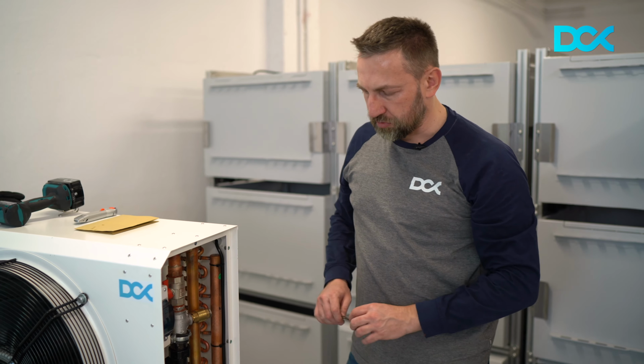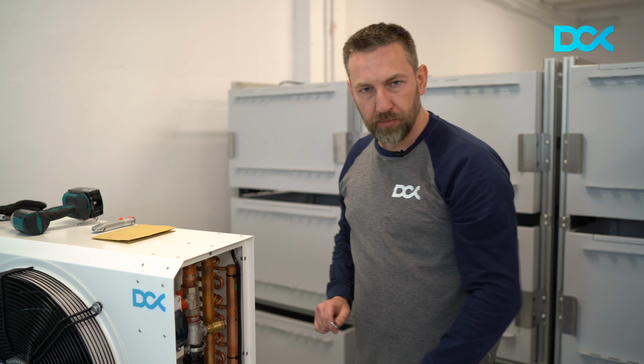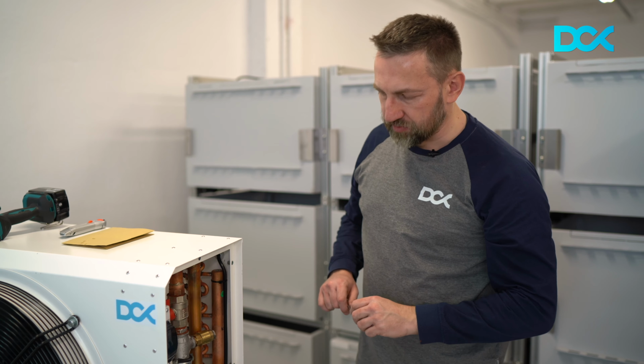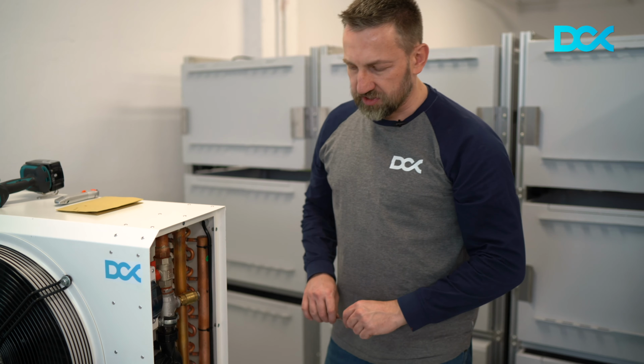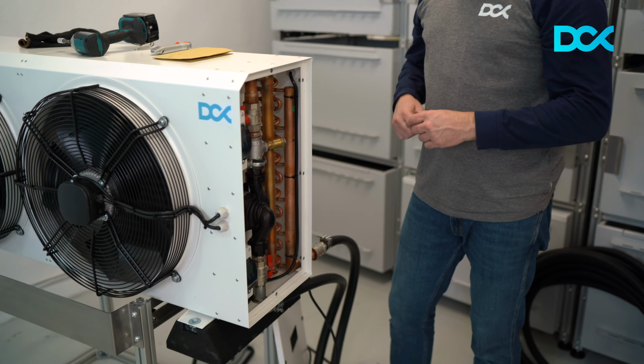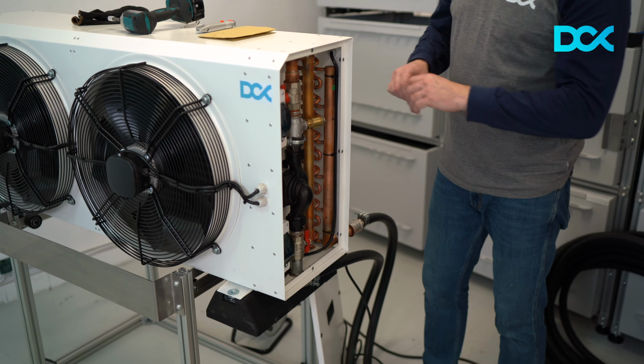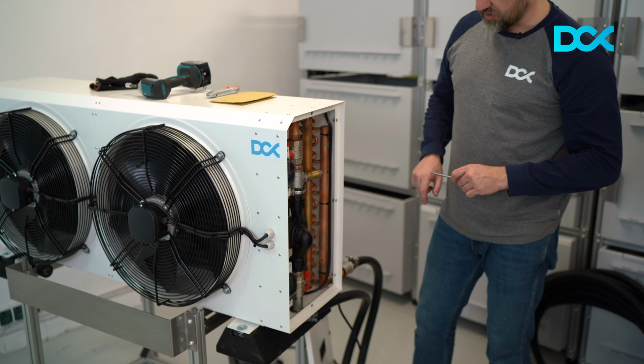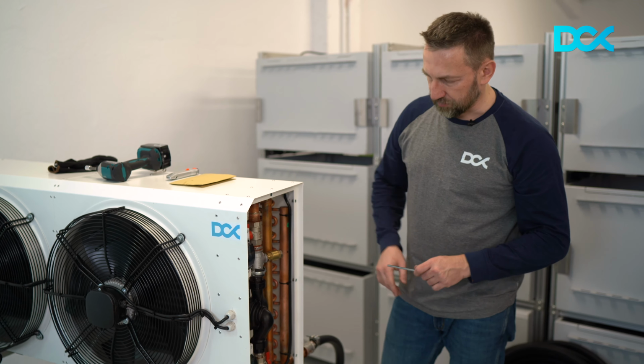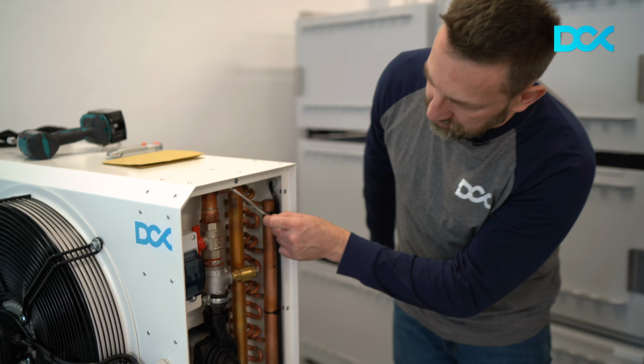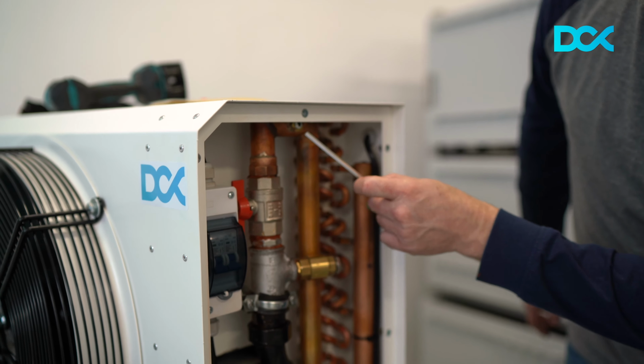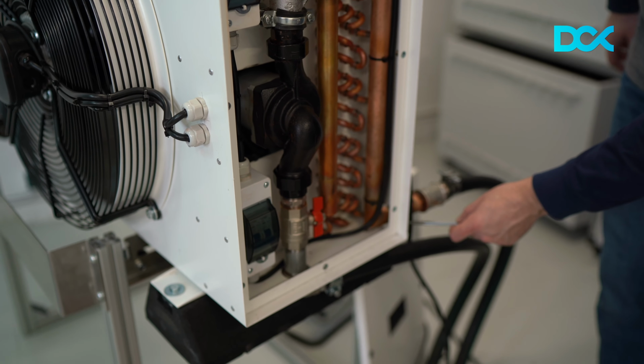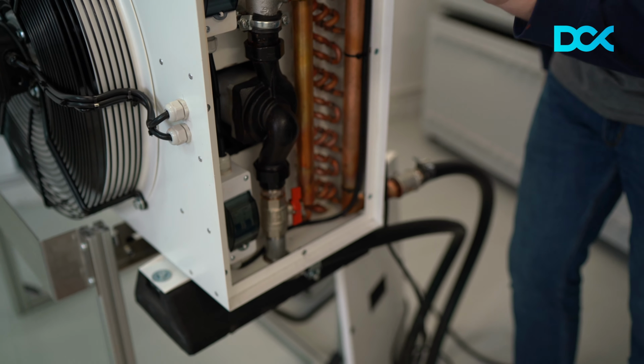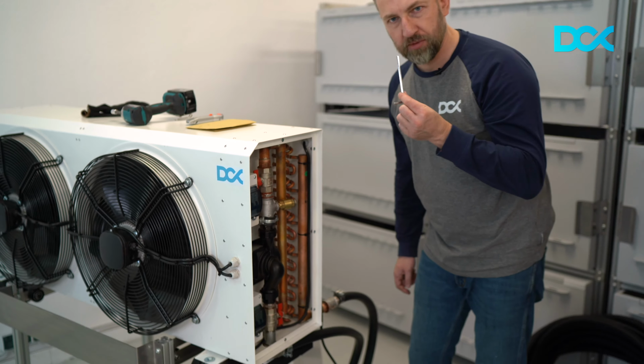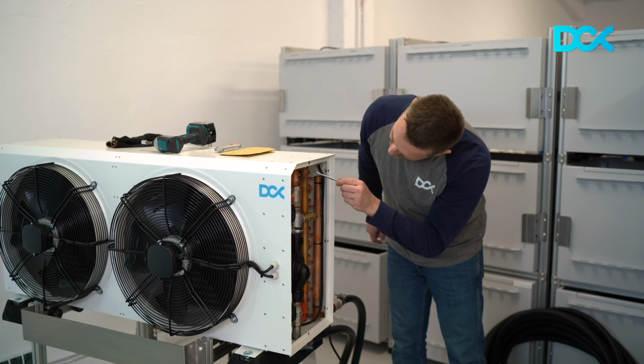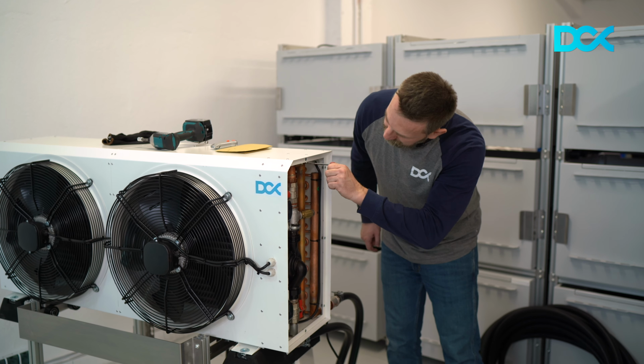So the only thing you need to do after you pressurize the system and you have 1 bar on the manometer of the manual pump is remove the air from the unit. As mentioned, the pump has a feature that releases the excess air from the pump head, but you may also need to remove the air from the dry cooler system. You have 2 air release vents, one located here on the inlet manifold, and the second one located here on the outlet manifold. All right, and you just need 1 key, the same which we are using for the rack. It's 5 millimeter. So for our US friends, we'll have that, so you do not need to look for it on Amazon or something.